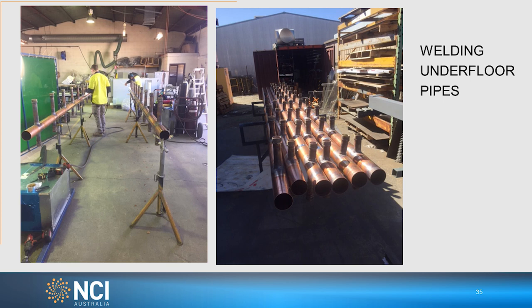Meanwhile, in a small place called Queanbeyan, just outside Canberra, one of the local workshops was starting to weld up the copper piping required for the cooling solutions. It's very important to know what metals are being used, given that we're going to have direct liquid cooling flowing through the machines. So water quality is one of the things we have to monitor, along with the type of chemicals and biofouling units that go in there.